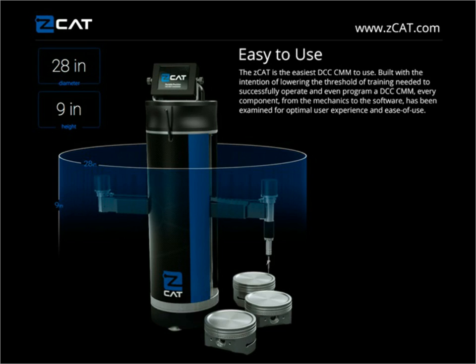The gauge will rotate actually 360 degrees, and you can nest parts all the way around it if you'd like to. There's a rotary encoder in the base, so when the gauge rotates 360 degrees, it will measure anything in that radius. We also have a rotary encoder in the probe for a 360 degree rotation in the probe as well. There are 2 linear scales, one in the Z-axis and one in the cross-axis. So I won't say an X-axis or a Y-axis because of the rotation we have, it creates the X and the Y-axis on a combination of the encoders and the scales.